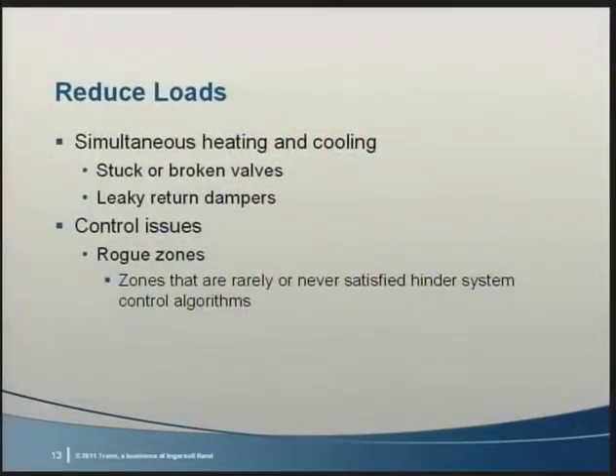If a dynamic control is looking at zones for making decisions and one or more rogue zones are never happy, the entire control may not work. The automation system may have provisions for removing rogue zones from polling or voting algorithms that reset static pressure, ventilation, or temperature set points. Next, overrides.